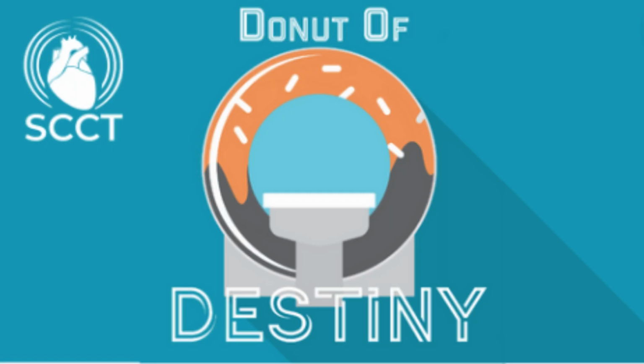The only caveat to photon counting, because everybody will always say, well, it can't always be perfect sunshine. You're not telling me the truth. Photon counting detectors, because they are a semiconductor crystal, operate when they are at the appropriate temperature. And when they cool down, their electrical properties change. And so we treat a photon counting CT just like you would treat an MR. You don't ever turn it off.